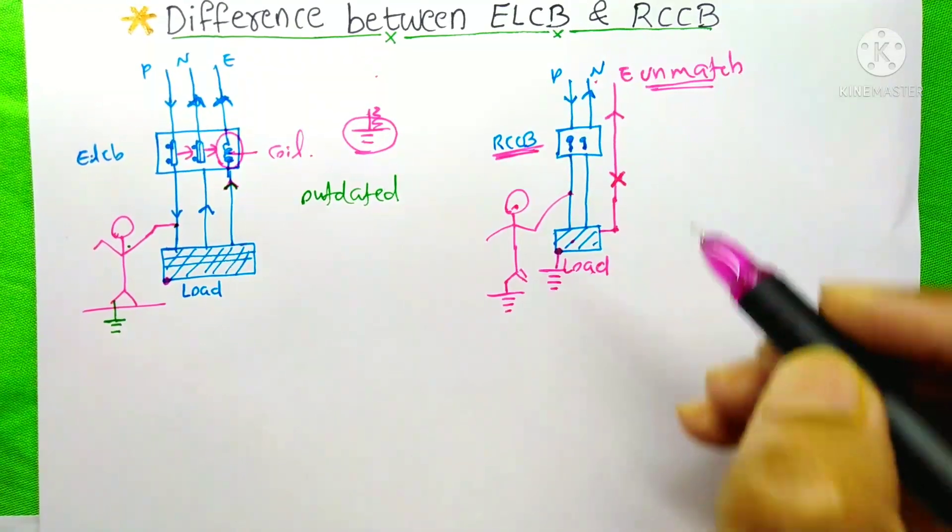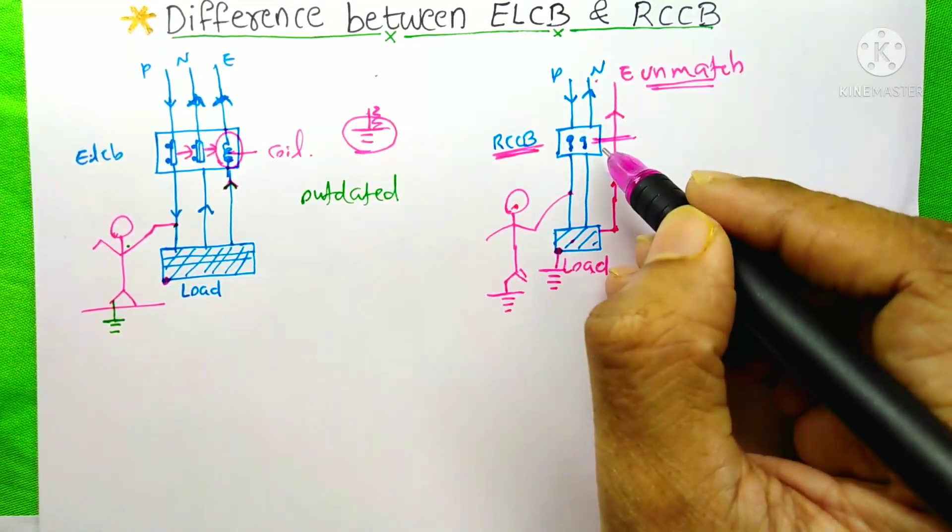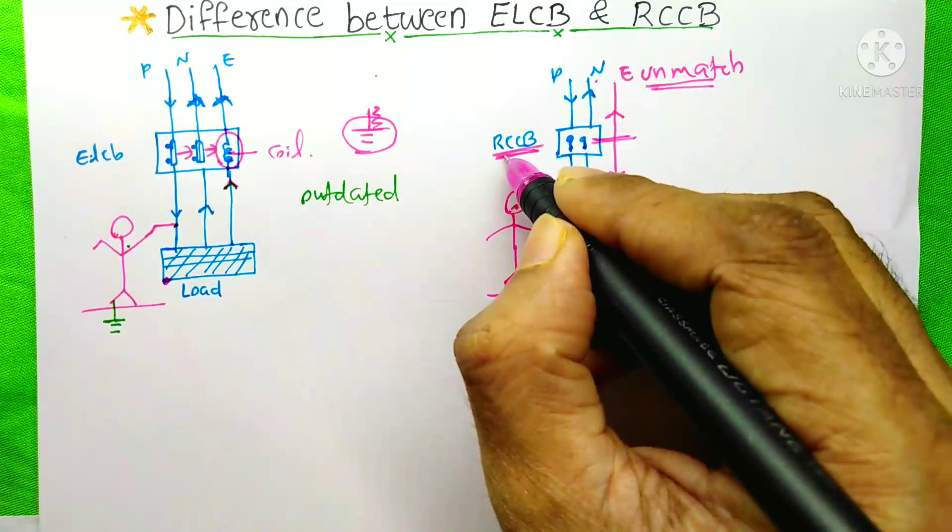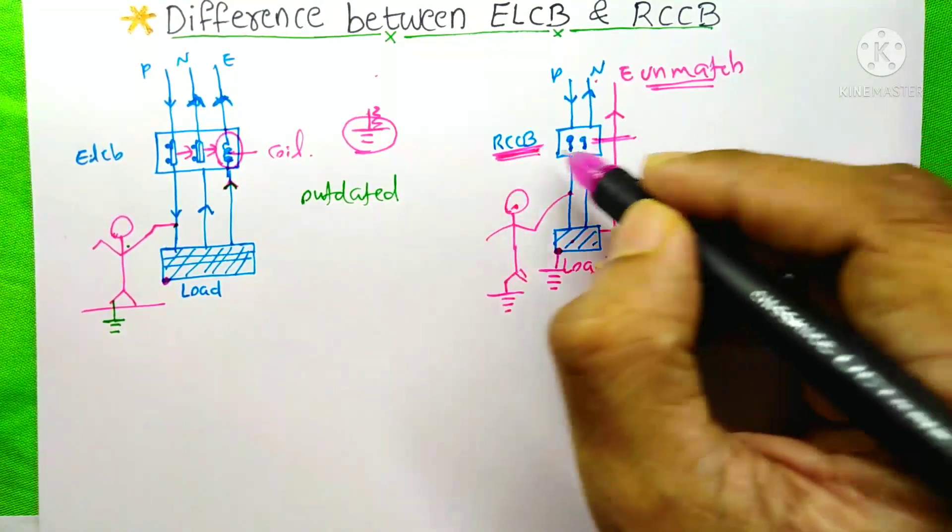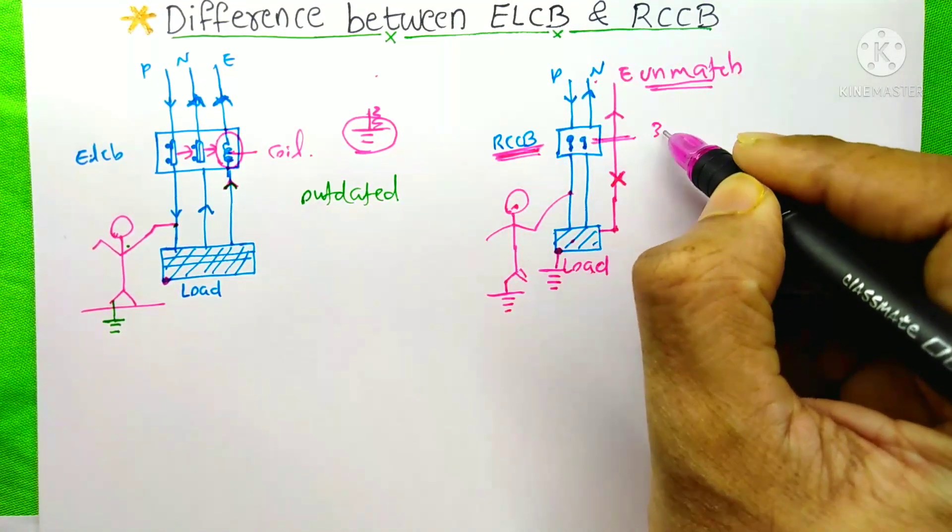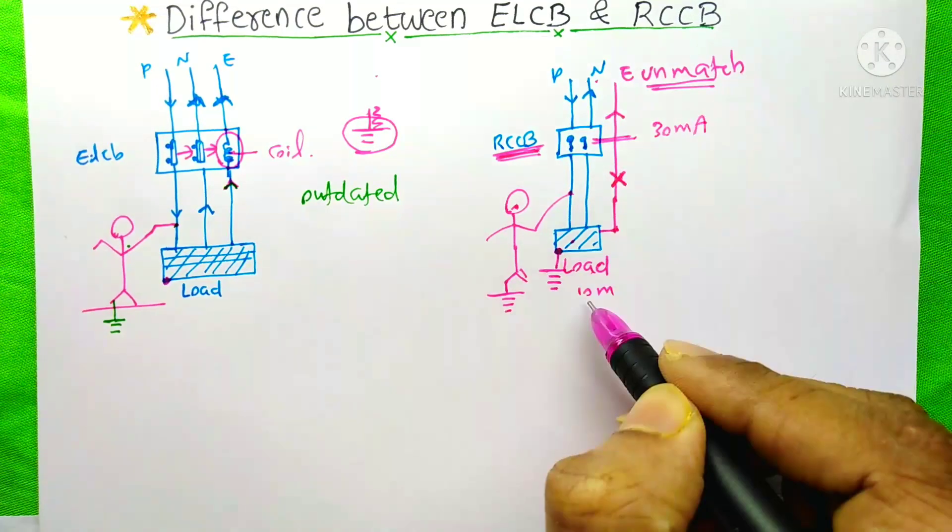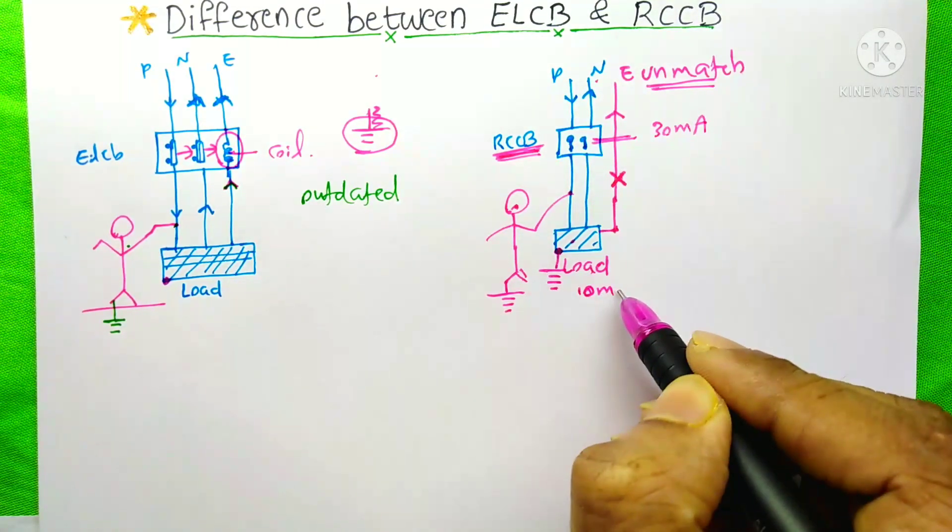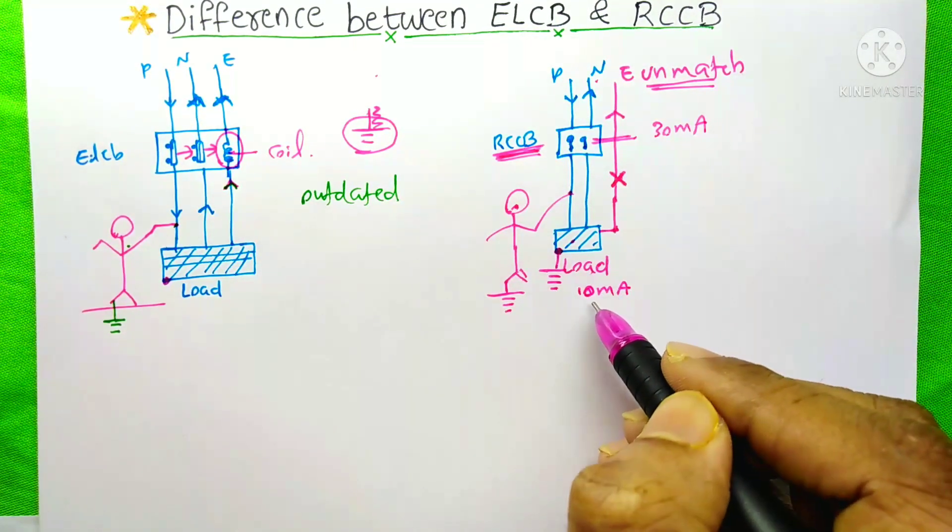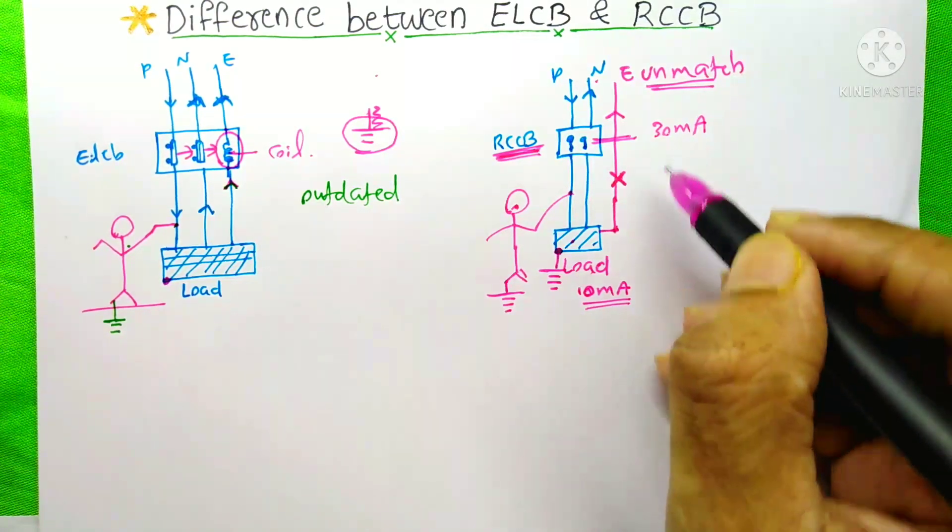And you know, for the tripping of this RCCB, the leakage current must be equal to the rating of this RCCB. Suppose the rating of this RCCB is 30 mA and only the leakage current here is 10 mA, then it is very low compared to this rating.